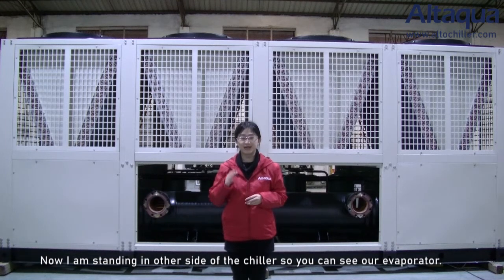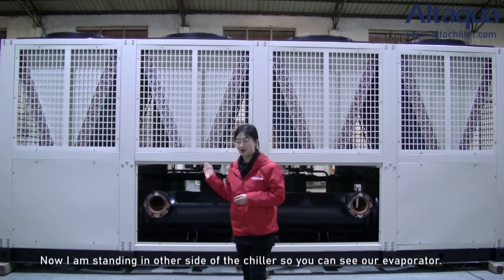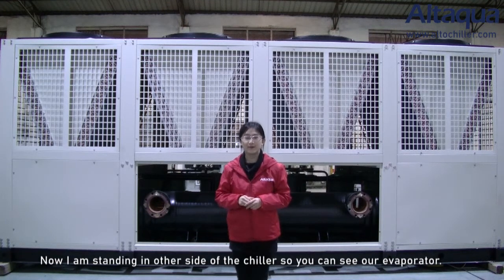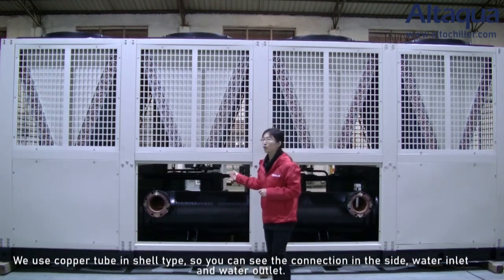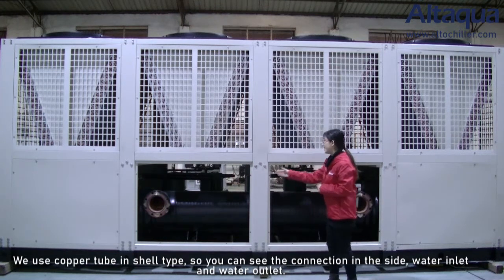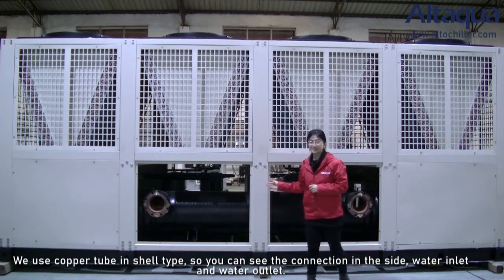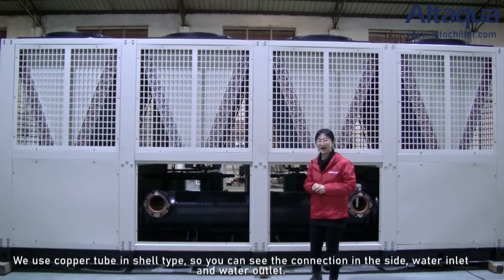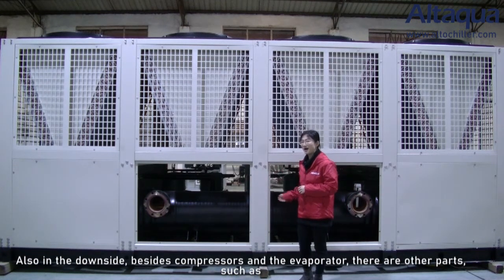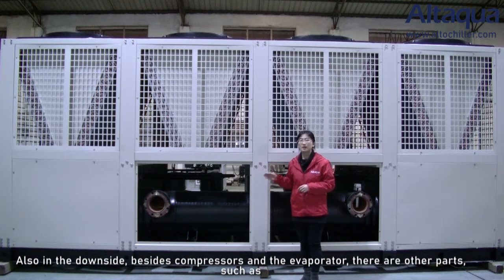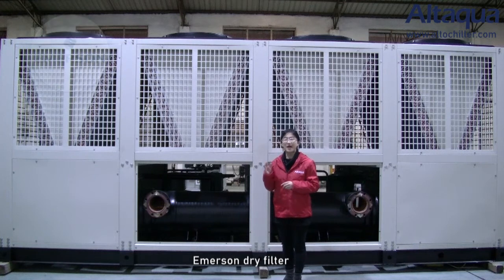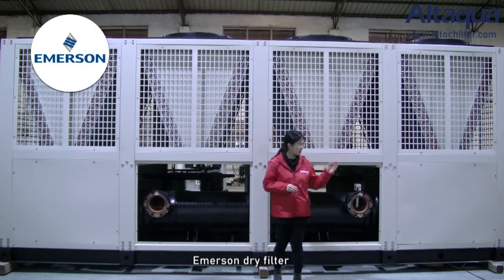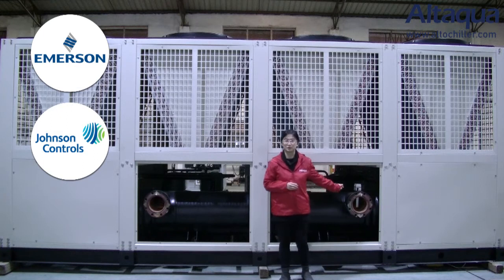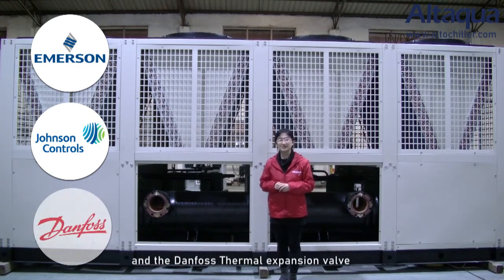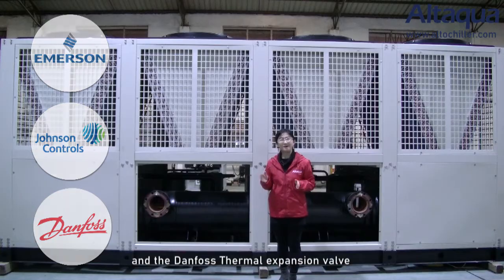Now I am standing on another side of the chiller, so you can see our evaporator. We use a copper tube in shell type. You can see the water connection on this side, water inlet and water outlet. Also on this downside, besides compressors and the evaporator, there are other parts, such as the Emerson dryer filter, Johnson Controls water flow switch, the Danfoss expansion valve, and so on.